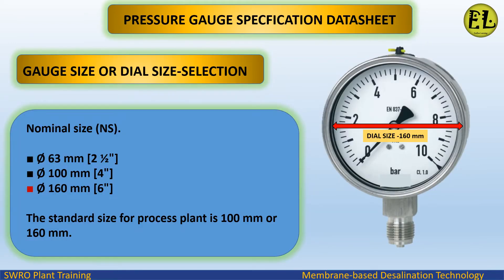Gauge size or dial size selection. Nominal sizes available are: NS 63 mm (2½ inches), 100 mm (4 inches), and 160 mm (6 inches). The standard size for a process plant is 100 mm or 160 mm. We select 160 mm for this application.